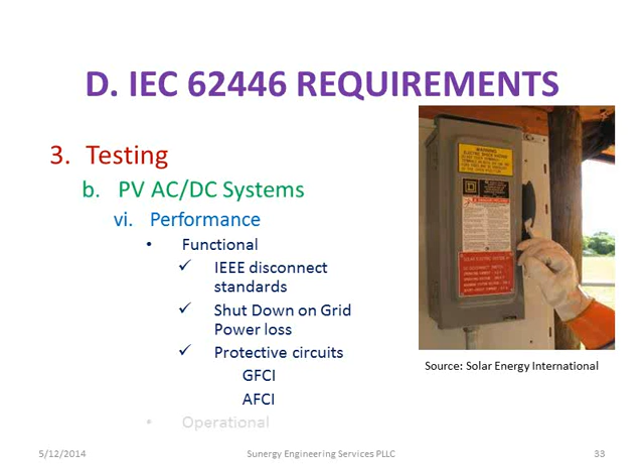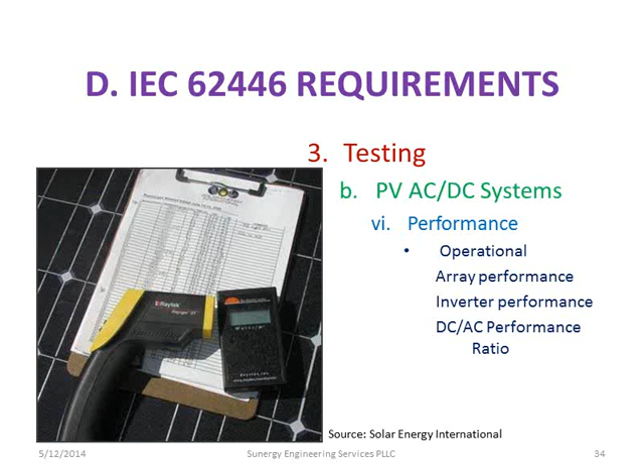And so for performance testing, you have to know what the irradiance is, and you have to know what the cell temperature is so that you can back out the STC values of what the module is supposed to be producing at standard test conditions. And without those two tools, this is a little, actually I have one up here too. It's just a little point. It's kind of like a thermal camera, but it only has one pixel. It only does one little dot to measure the cell temperature, and you need to have a way of measuring the irradiance so you can back it out. And a lot of these special tools that I'll show you have that all built in, so you don't have to worry about it.